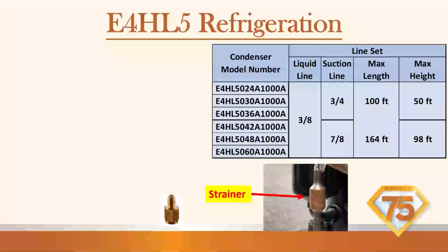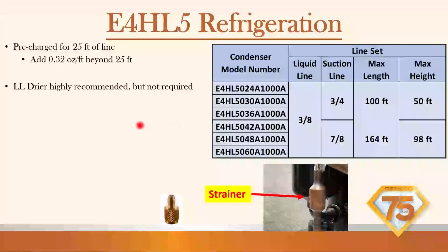Now, would it have been easier and saved a lot of time if they had an external 3/8 filter line dryer on it? Yes, it would have. So that's what prompted me to ask the factory if we could use a filter dryer on these installs. The pressure drop does not affect the system. So with that being said, I recommend using a filter dryer, but it's not required because of these strainers. But if these strainers get plugged, because there's more than one in the outdoor unit, it's a lot harder to swap these out than it is to swap an external dryer.